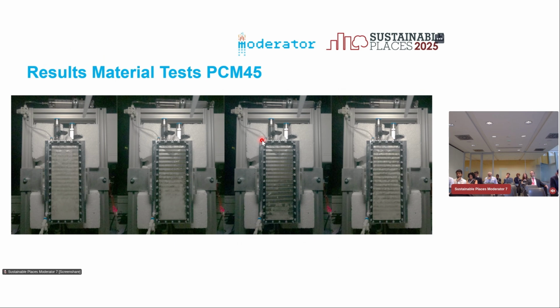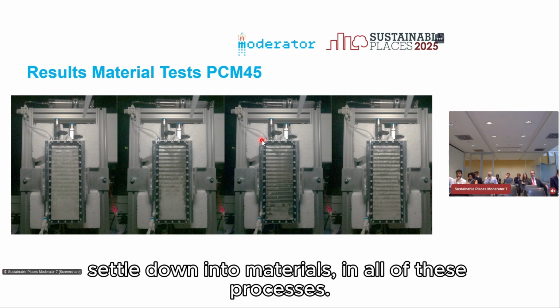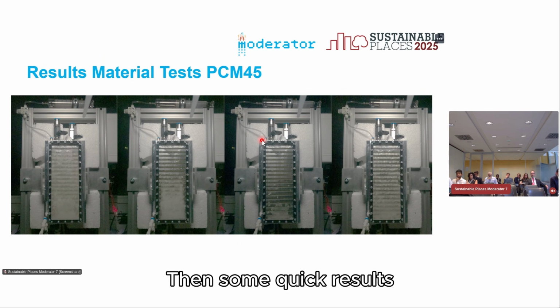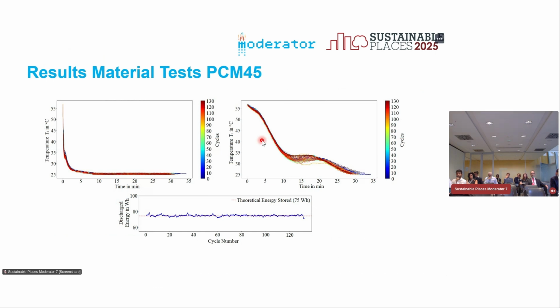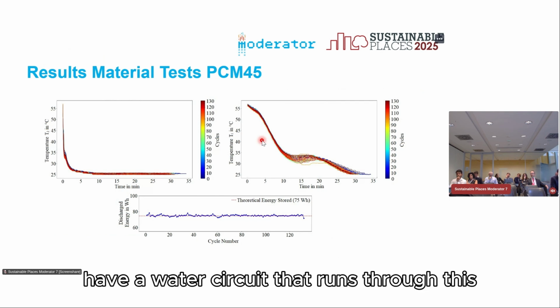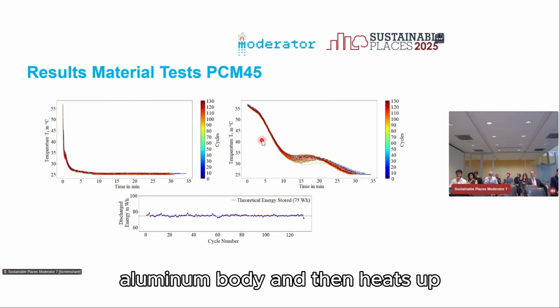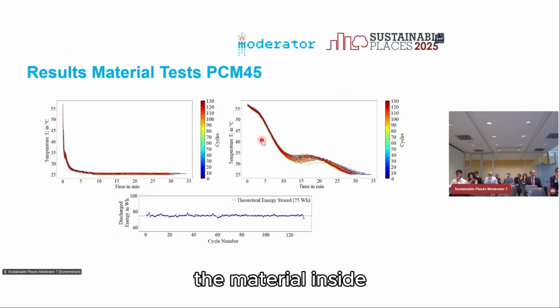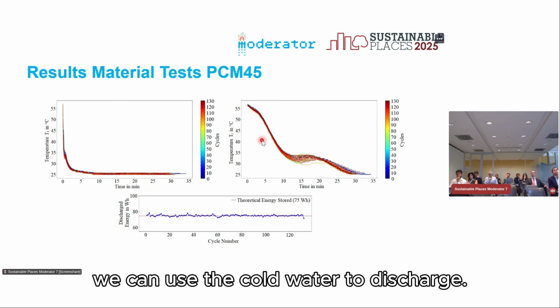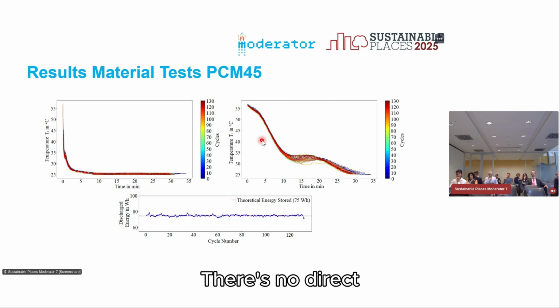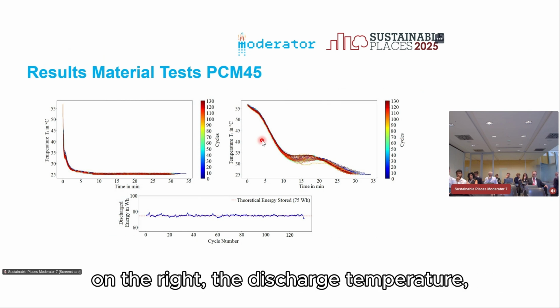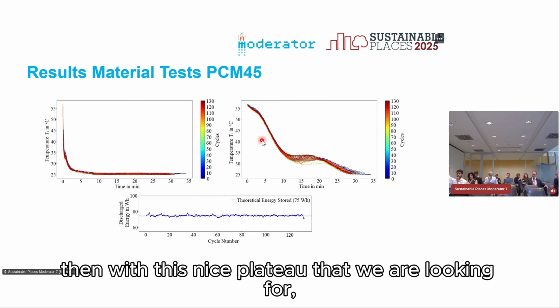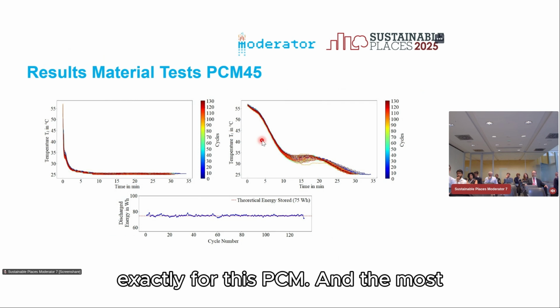And here it's also really important to observe visually how the material behaves. So do we have segregation? So do the additives settle down in the materials and all of these processes? Then some quick results on the performance of this mini cell. The way this is operated, we actually have a water circuit that runs through this aluminum body and then heats up the material inside the aluminum body, and also we can use the cold water to discharge it again. There's no direct contact between the water and the PCM, so it's all within this aluminum body. And on the left, you can see the inlet temperature of the water, and on the right, the discharge temperature then, with this nice plateau that we are looking for, exactly for these PCMs.